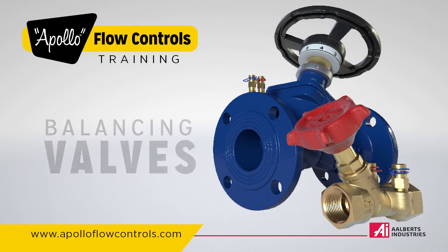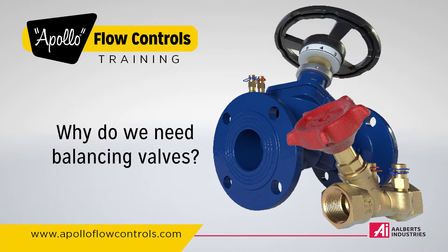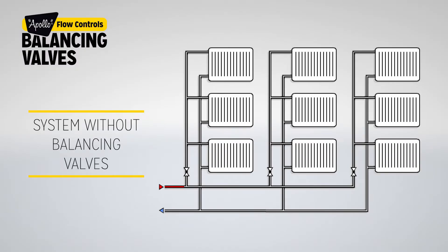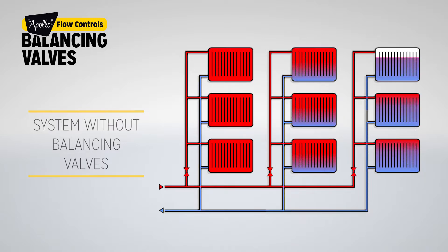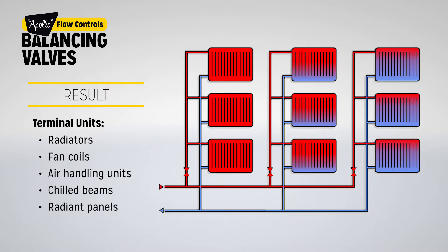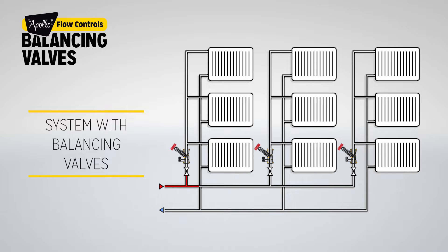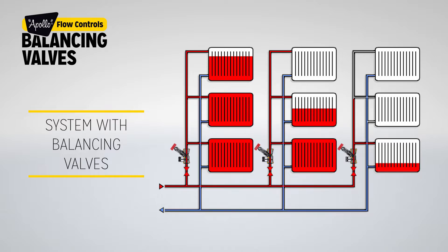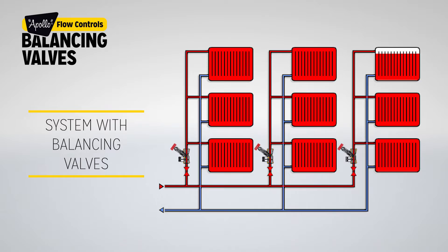Balancing valves: why do we need balancing valves? When the system is unbalanced, water takes the easiest path through the system where the resistance is lowest. Terminal units such as radiators, fan coils, air handling units, chilled beams, and radiant panels that are closest to the pump are provided with excess water flow, while units farther away from the pump receive insufficient flow. When balancing a system, flow distribution is changed so that critical circuits can be provided with the required flow, and the whole system is in balance.